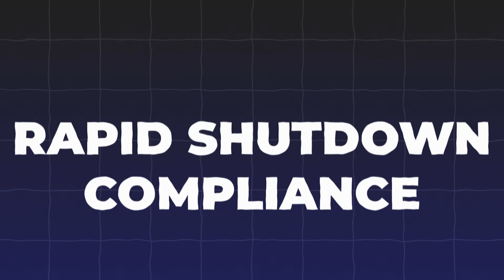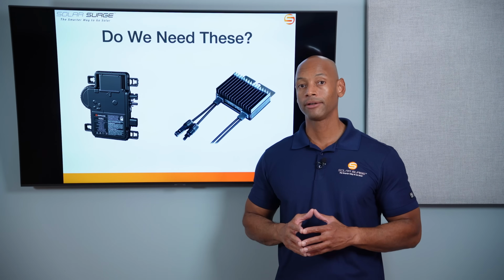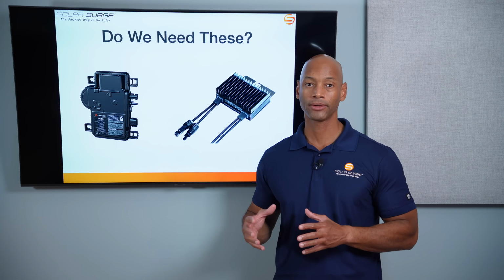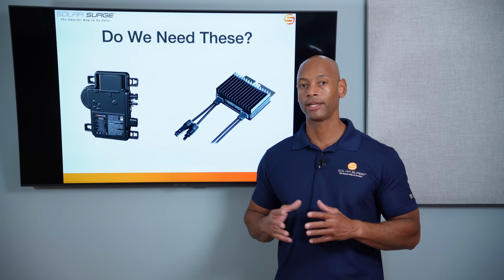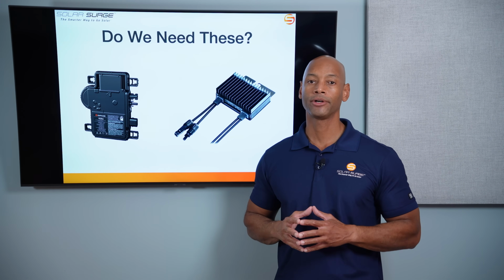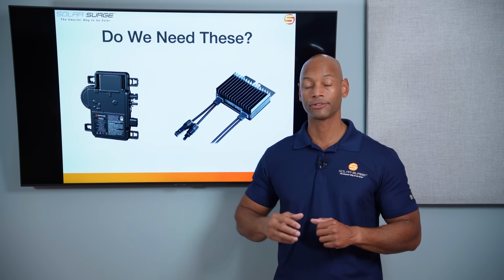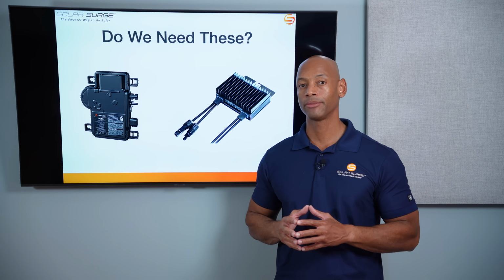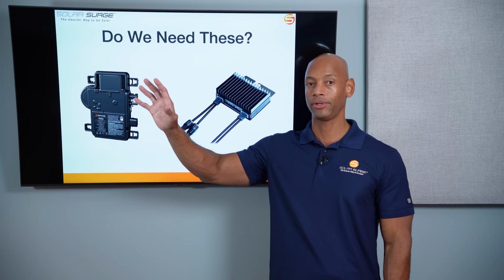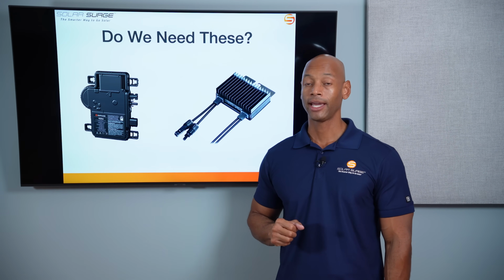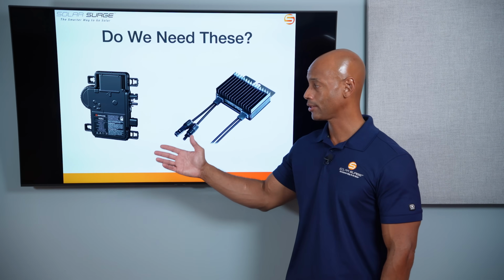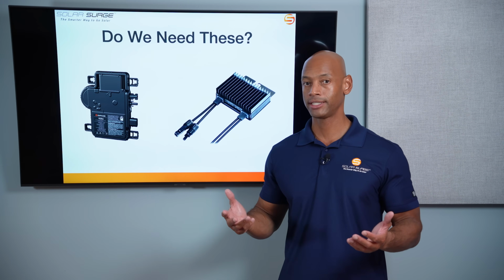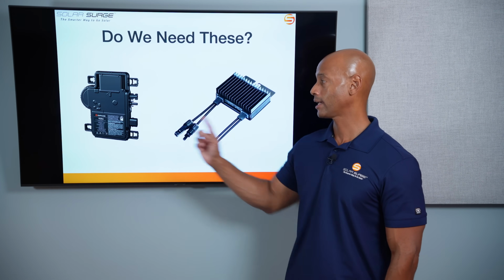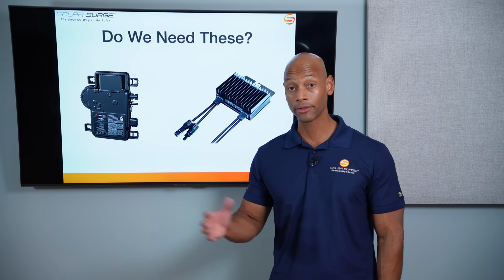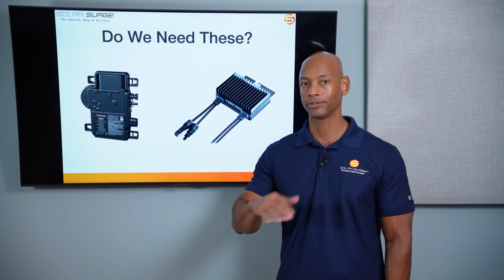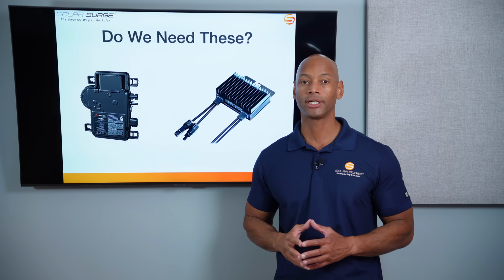The third benefit is rapid shutdown compliance. Rapid shutdown is part of the National Electric Code that governs solar. It's designed to ensure that if the fire department has to come to your home and pulls the electric meter to shut off power, the high voltage from the solar has to be disconnected within 10 feet of the array. Module-level power electronics on each panel inherently do this, because as soon as the grid signal goes out, power is cut directly at the module-level electronics—right underneath each solar panel, the high voltage output is cut off—so you get that rapid shutdown compliance.